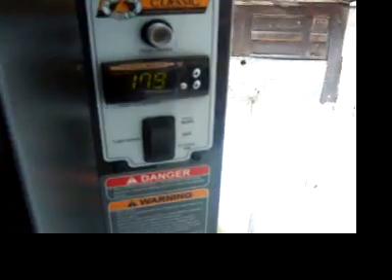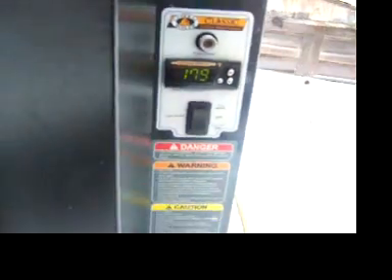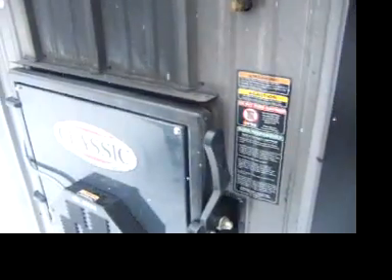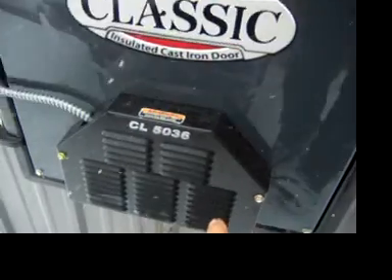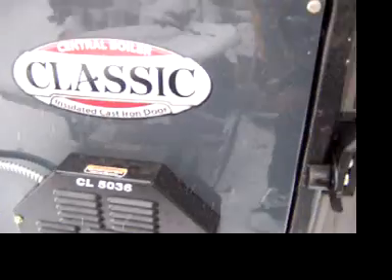It actually has an electric thermostat on it. It can't make the furnace heat any quicker, but when it drops down — it's usually at 183, 184 — that's how hot the water is right now. When it tells it drops down, it has an electric damper that automatically opens on the door, and it starts letting the fire burn more.